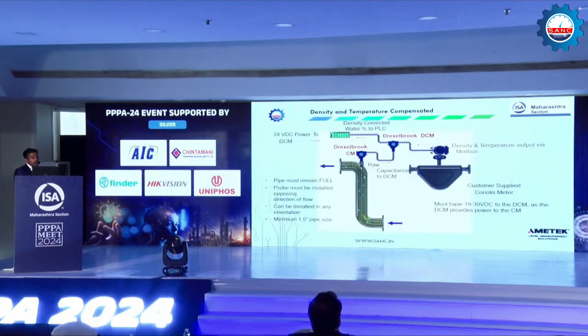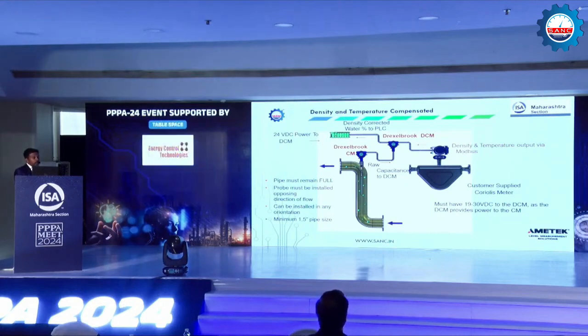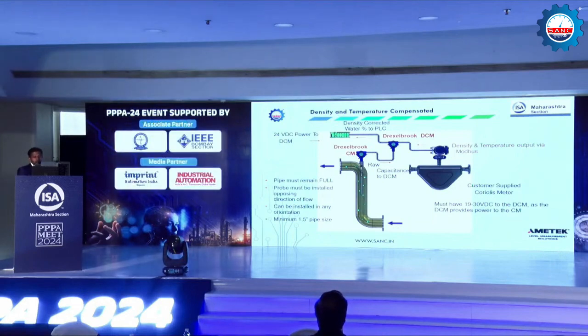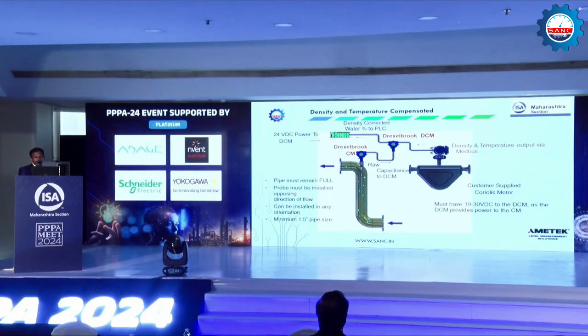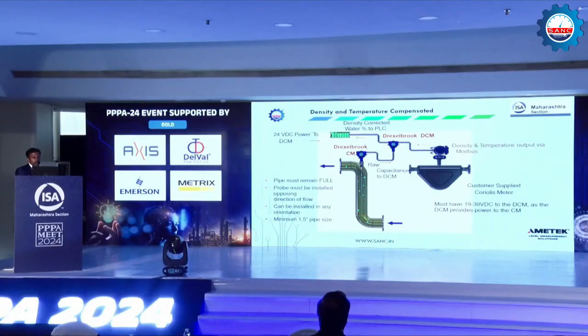There is one more problem when you are measuring the water content precisely: density and temperature could affect the measurement. To solve this, Drexel has a DCM model, the density corrected model, which accepts density data from the Coriolis mass flow meter. Density and temperature can be given to the DCM model, so it compensates the value and gives the actual water percentage.